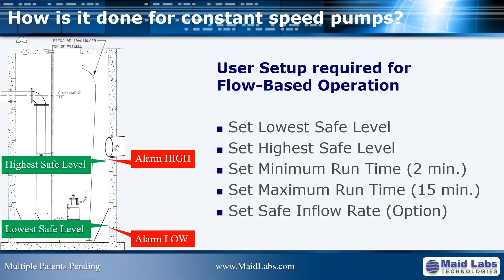So how is it done for constant speed pumps? So let's see the first situation when the flow coming in is low, which is most of the time, we have to say. The average head we had before is here. What will happen is that the head will move there. So by doing this, it means the head will get lower, and by having a lower head, the pump capacity will increase. And so it's a matter of starting the pump at the highest safe level and stopping it after the minimum run time that you specified. Again, when the flow rate is low, you should run the pump with the lowest pump capacity at that level first. Then, of course, when the flow rate is high, you should run the other one.